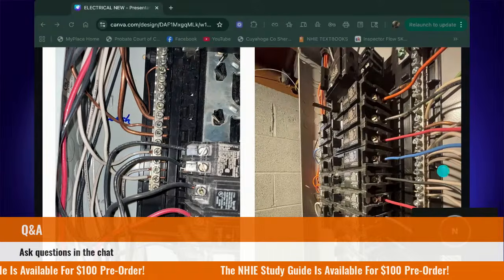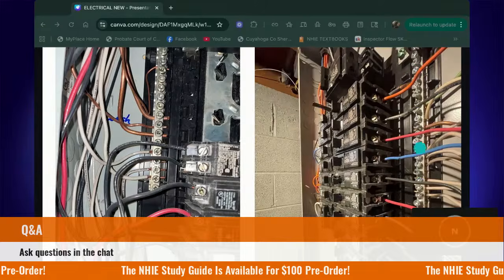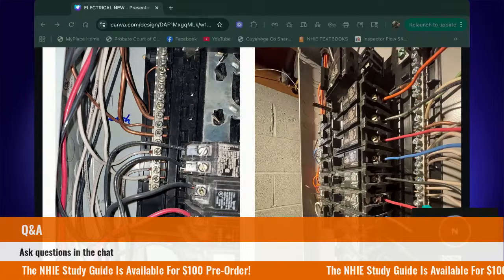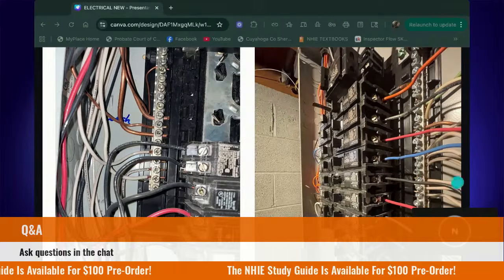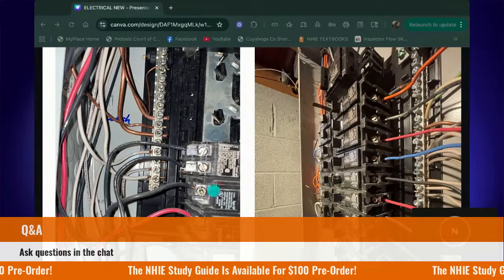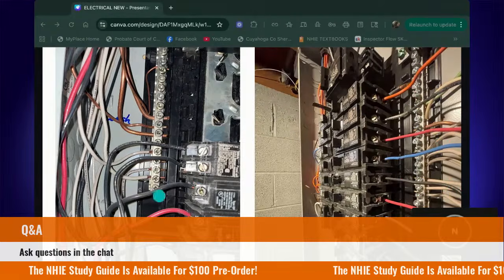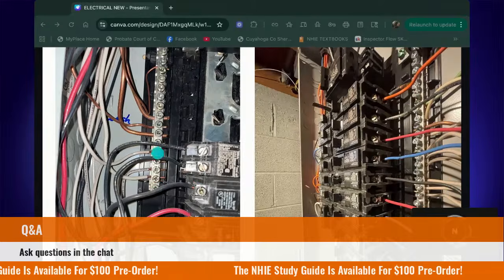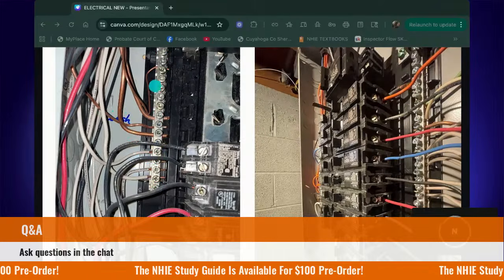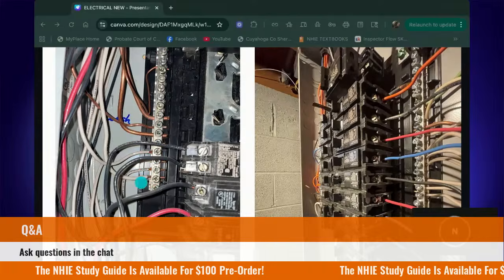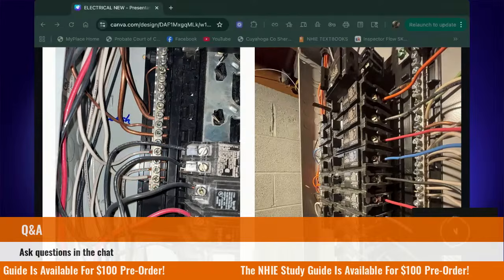Okay. So here on the right, this is a neutral bus bar. We know so by the white wires that are terminating on this bar. Here is also a neutral bus bar, but there are some ground wires terminating on this neutral bus bar. Is that acceptable? Yay or nay?